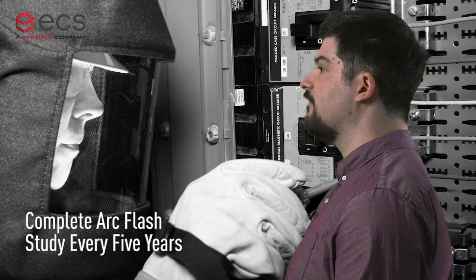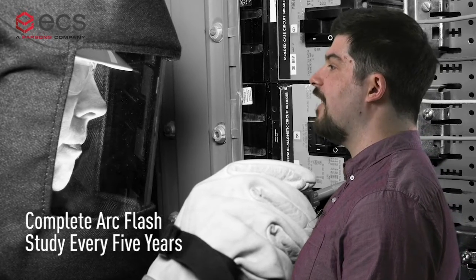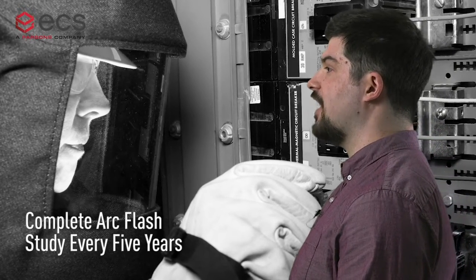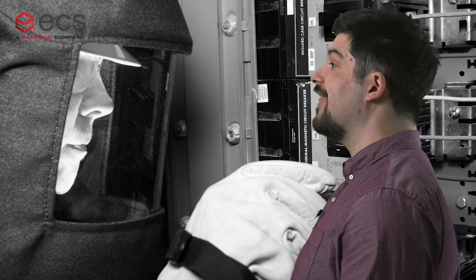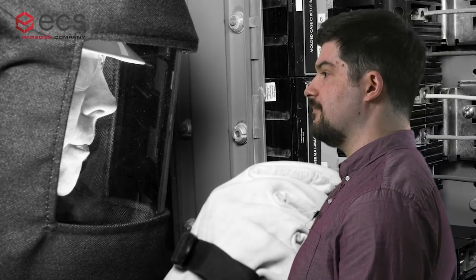The Standard for Electrical Safety in the Workplace, or NFPA 70E, states that arc flash studies should be updated every 5 years and at the time of any change to the electrical system. That includes adding or moving equipment.